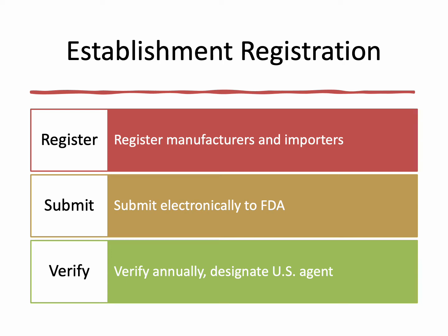Registration is submitted electronically, unless a waiver is granted, and must be verified annually between October 1 and December 31. Foreign manufacturers must designate a U.S. agent to facilitate FDA communication. For example, a Canadian manufacturer of diagnostic kits must register and pay a fee, required since 2007.